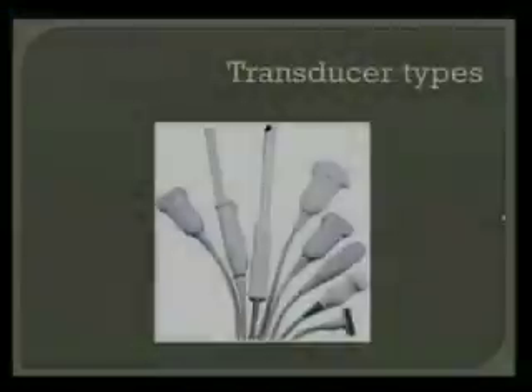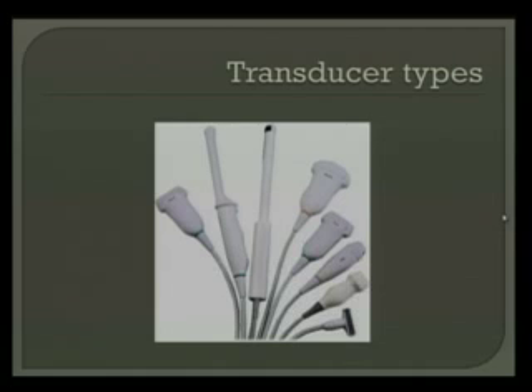Exactly. So a transrectal TRUS probe, which is used for examination of the prostate, is usually side-firing because you're not really interested in the rectum because you're not going to see anything. So you only want to look anteriorly. When you're in the rectum, you only want to look anteriorly to the prostate. You don't want to look at the sacrum or anything. So that's true. This is a regular curvilinear probe. Look how the face is curved. And this is a lower frequency probe, 3 megahertz to 6 or 7 megahertz. This is used for abdominal imaging.